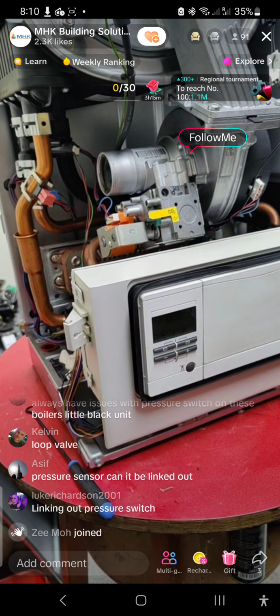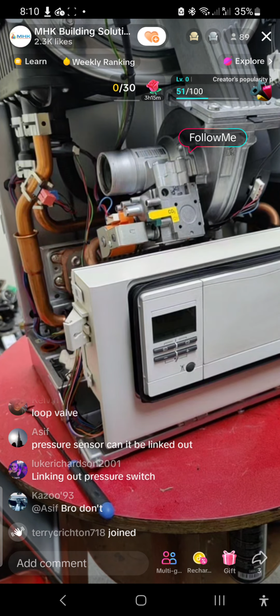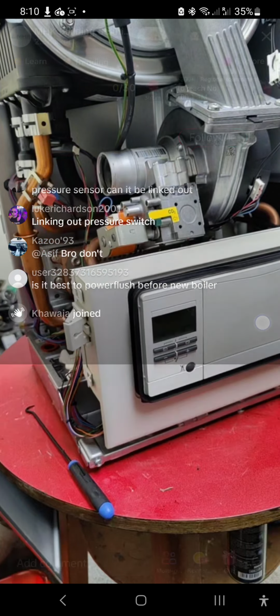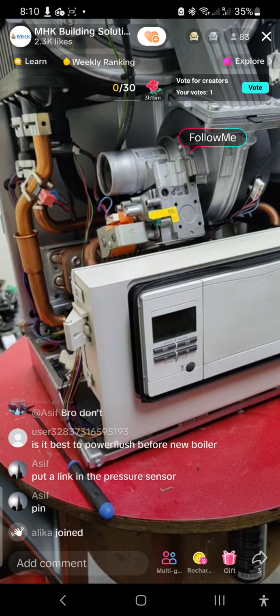Kelvin loop valve, pressure sensor - can it be linked out? To my understanding the pressure sensor cannot be linked out, because it moves, and with its reading it tells the boiler how much pressure there is. So we're not linking anything out.